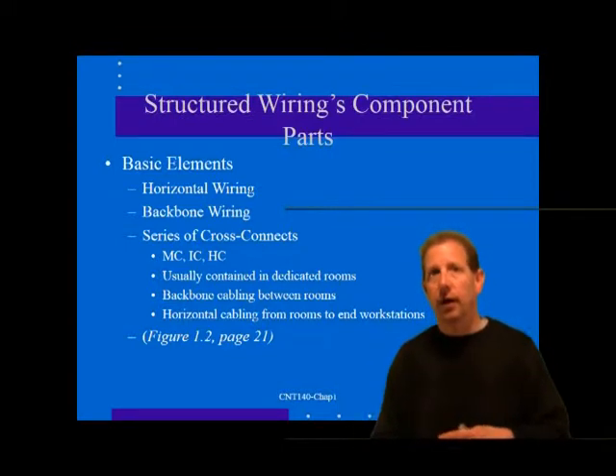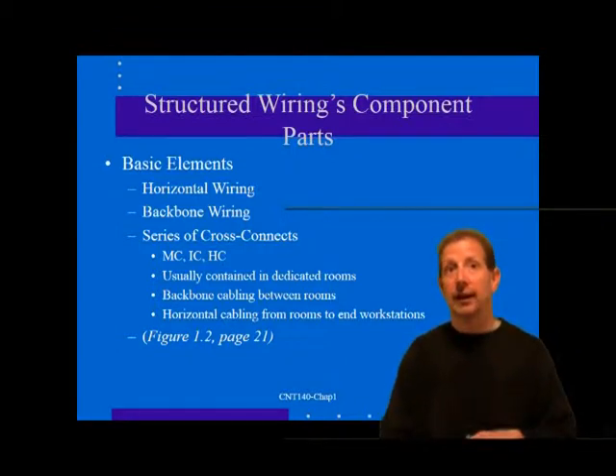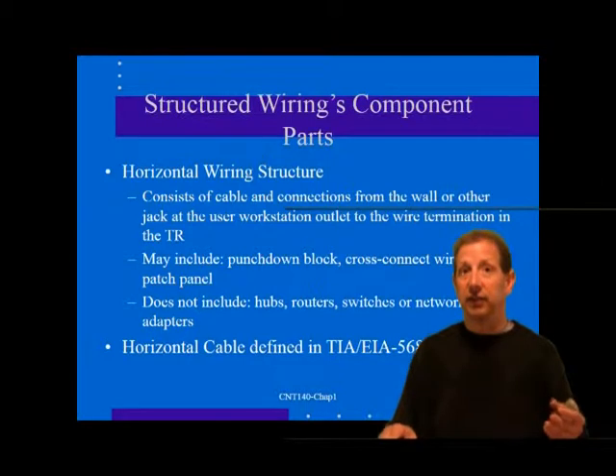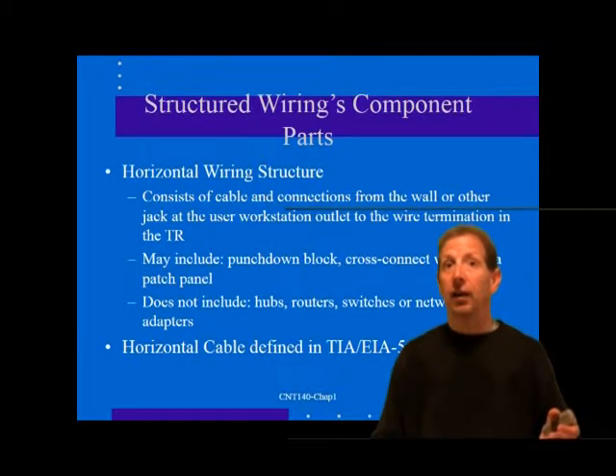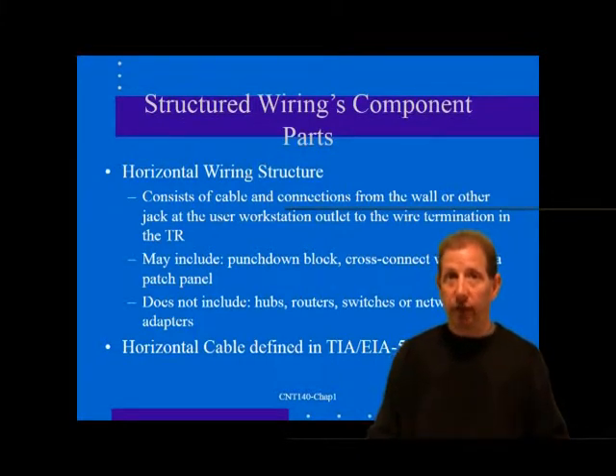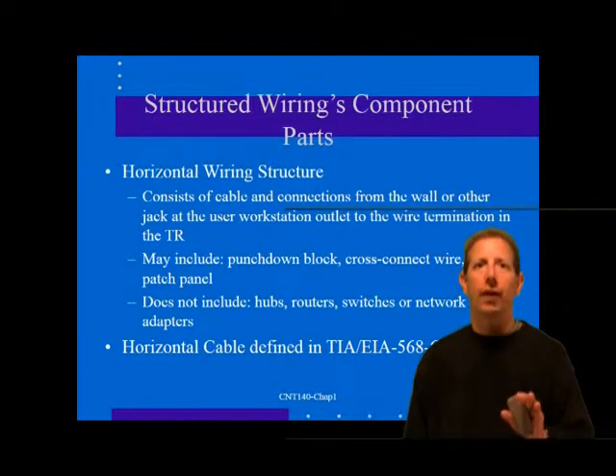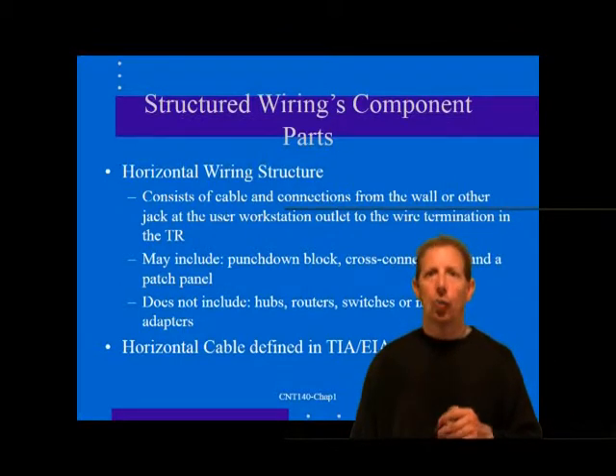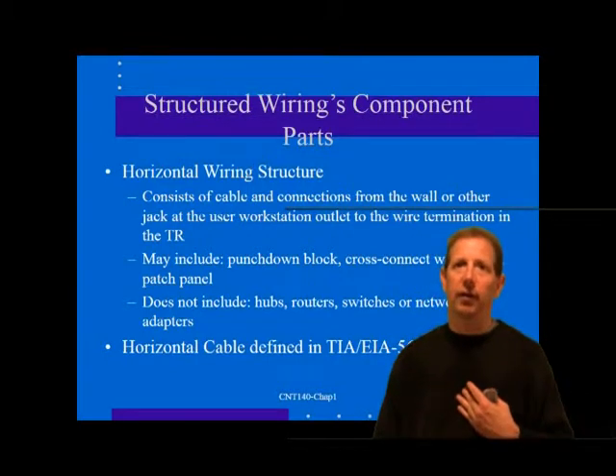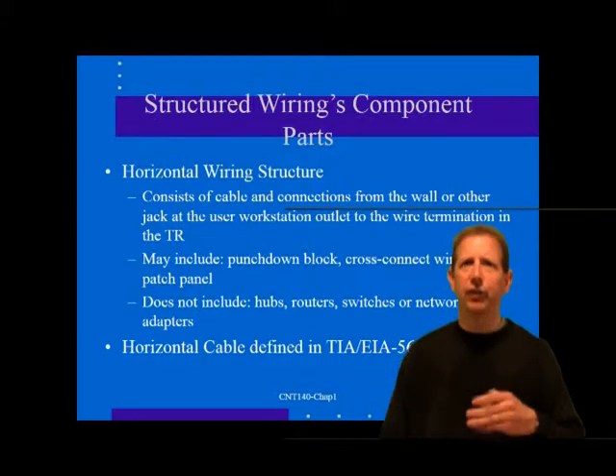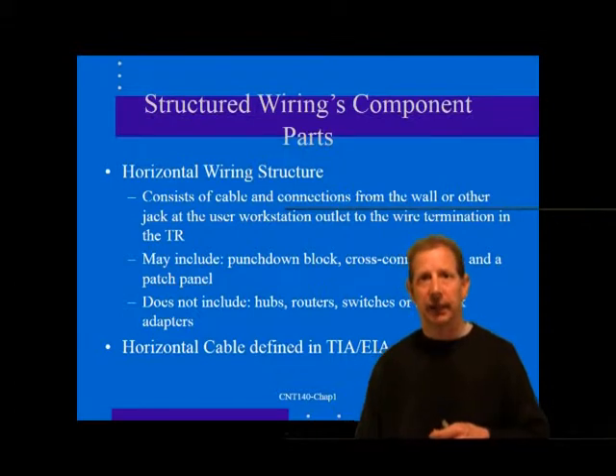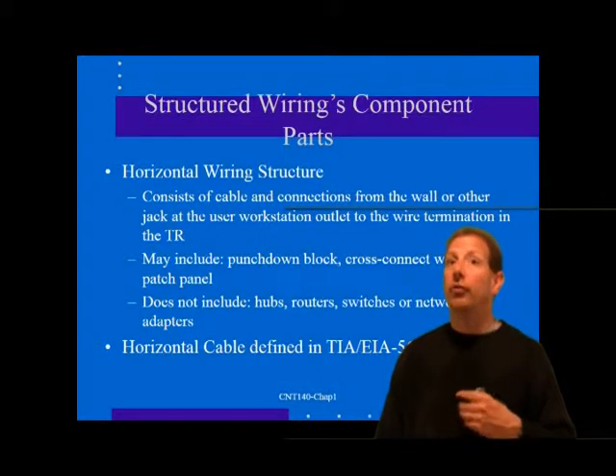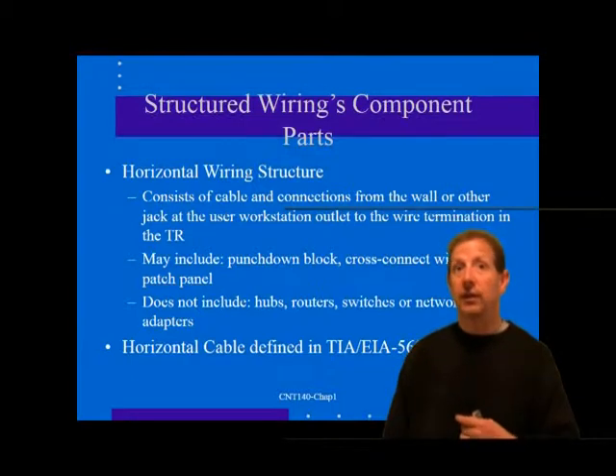Although the structured cabling concept actually comes from the telephone industry — predating data uses of twisted pair cabling — its use is particularly critical to modern data networks. Structured wiring defines precise maximum distances, types of connections, grade of cable, connectors, and the installation practices necessary to provide reliable, flexible data and voice cabling infrastructure. The embodiment of modern structured data/voice wiring is the 568C standard for North America and the ISO/IEC 11801 standard for the European community.